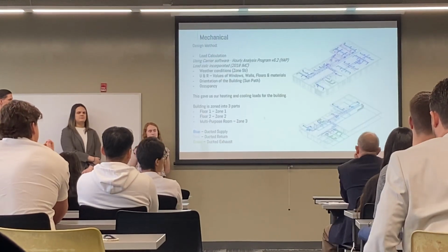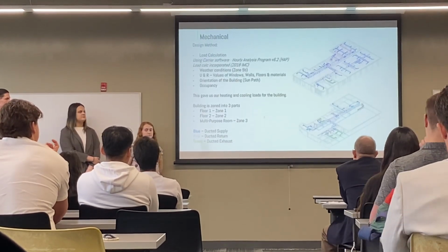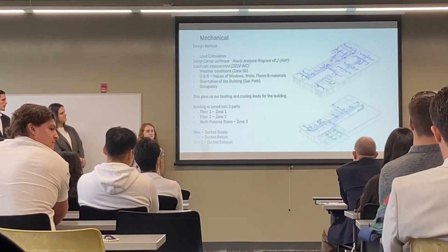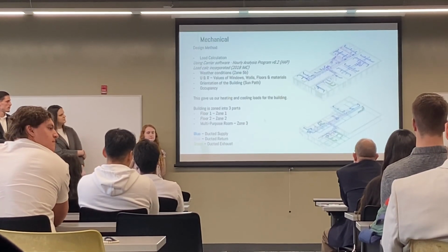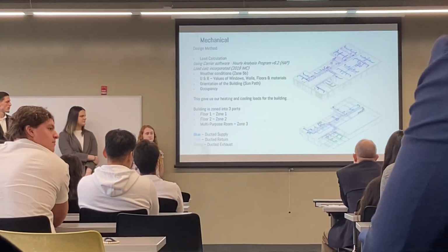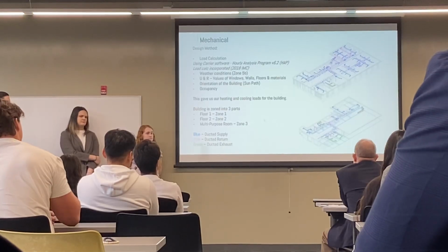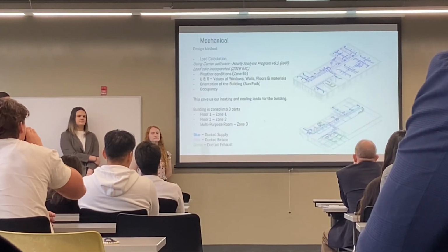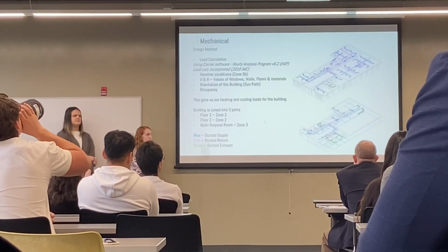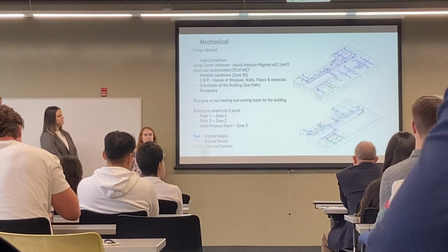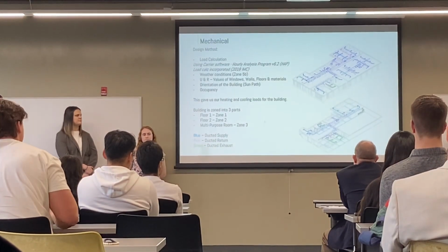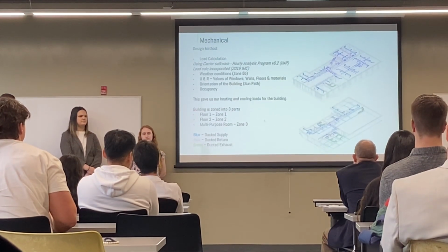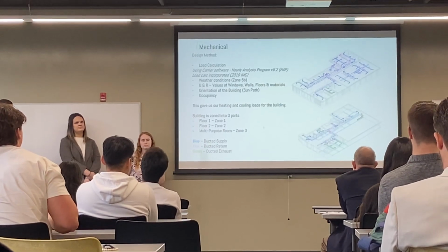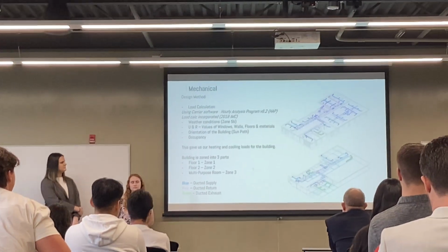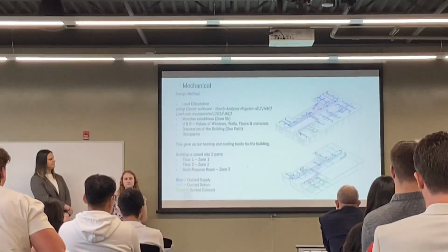Little things about the load count, but the main things of it, pretty much we have to include the weather conditions for this area. Also include the U and R values of different materials that are going to be surrounding the building. So walls, windows, floors, and knowing the U and R values of those. Also knowing the orientation of the sun, as Blas previously mentioned. And knowing the occupancy load that will be throughout these specific floors. Once that was all completed, this gave us our heating and cooling loads for the entire building.